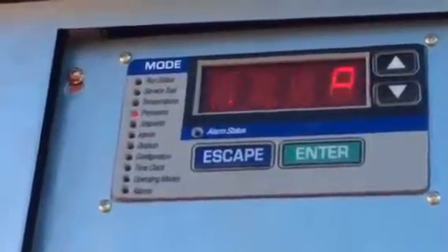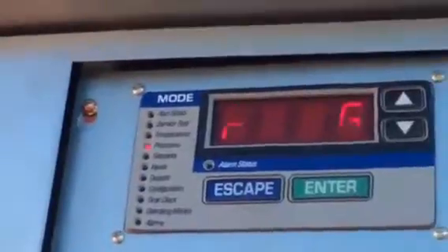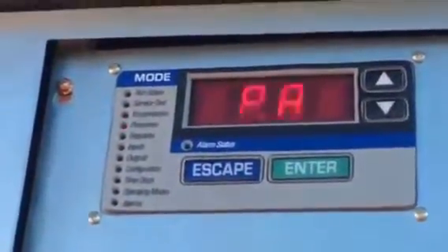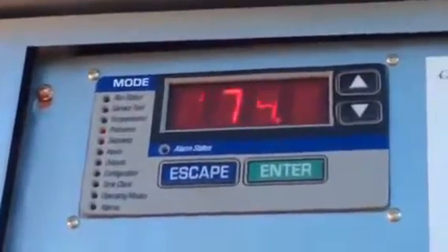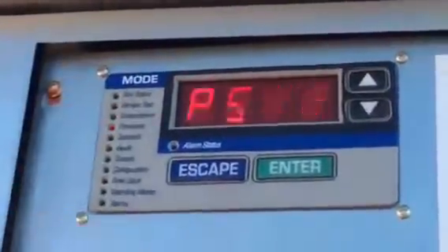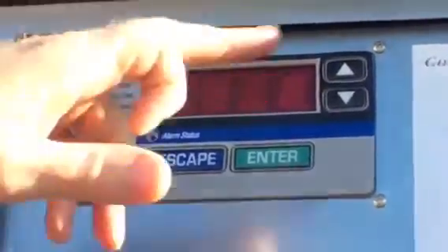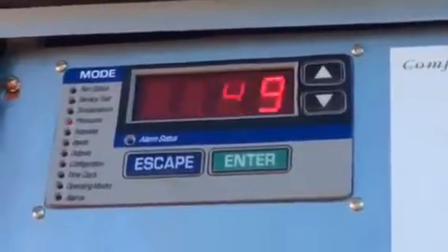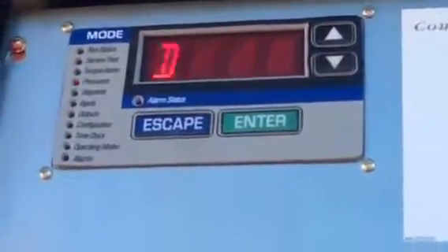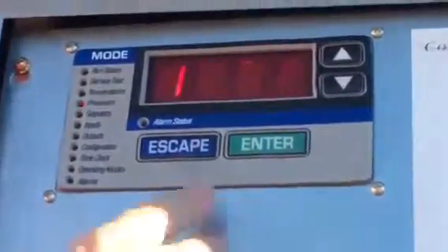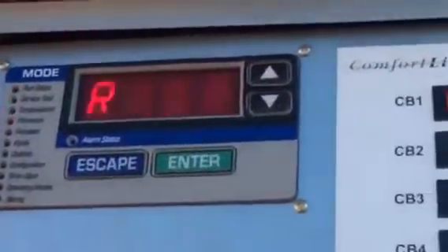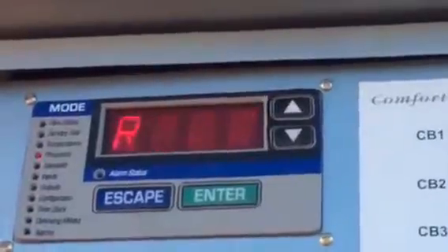So I don't need to hook up gauges or temperatures on this machine. I can read them directly off this marquee. Or for you guys, when you get the handheld, it's exactly the same structure, except instead of having to scroll by, it's going to give you 4 lines, all the information at once. And so it's right in front of you. You can stay standing on the ground. So you can tell if this thing's flat. Yeah, I can actually call up the pressure and look.